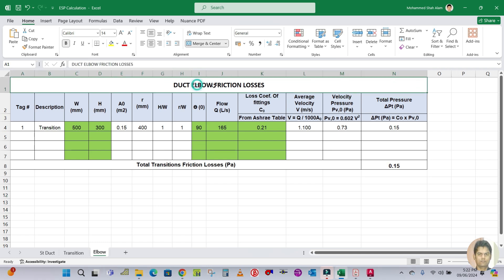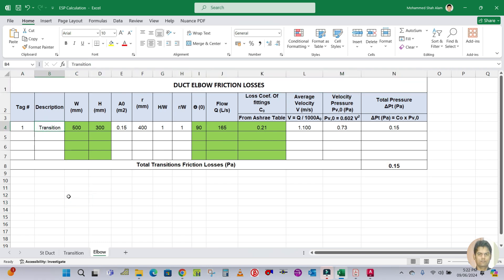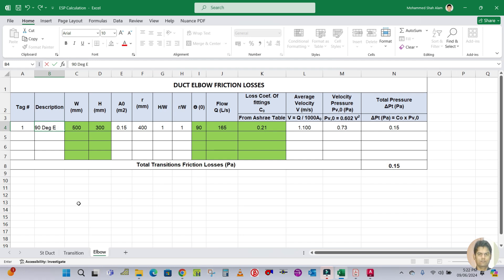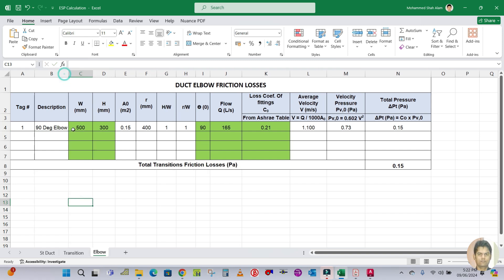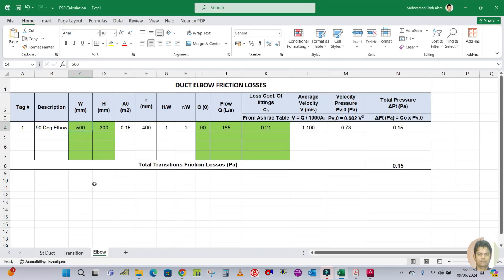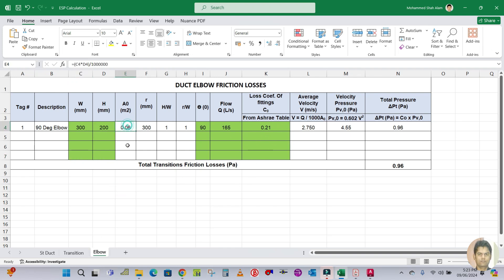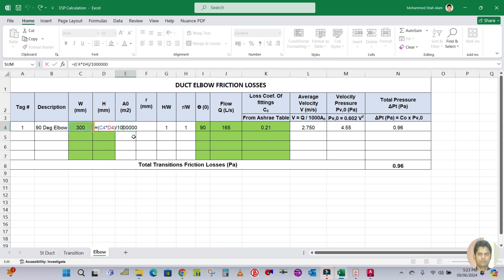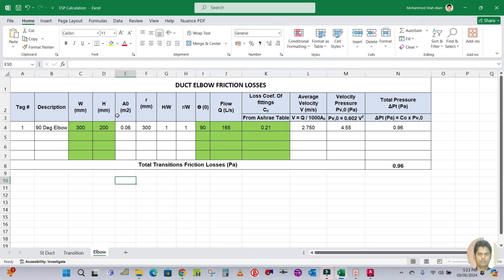In this Excel sheet I have prepared you can see the duct elbow friction loss. The first column is tag number, then description — write '90 degree elbow'. W is the width of the elbow and H is the height. From the drawing, width equals 300 and height equals 200. Enter these values. The green color is user input — do not touch the white cells, as those already have formulas set.